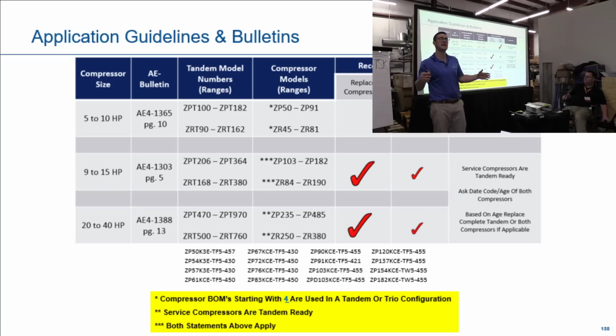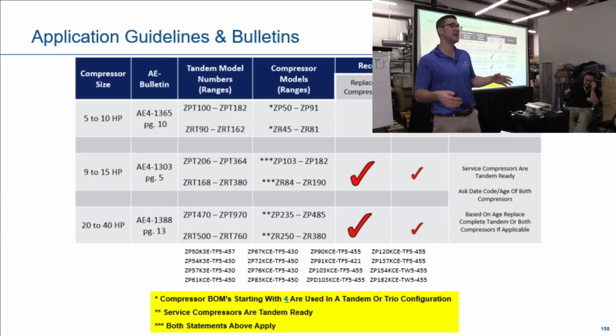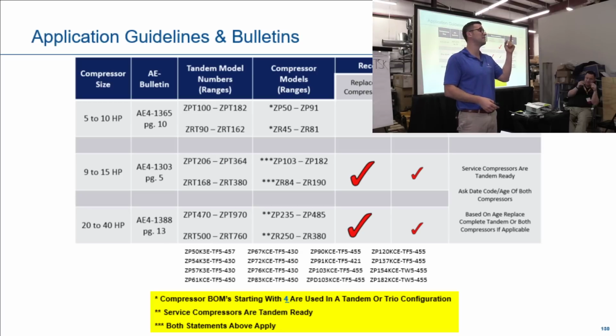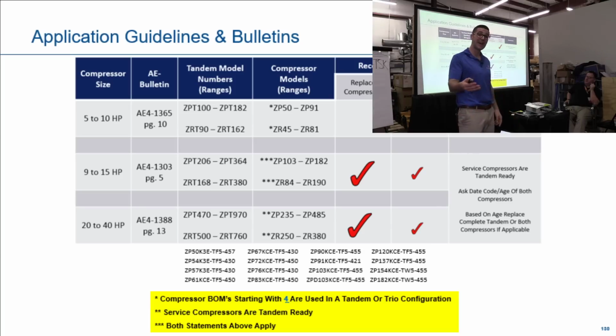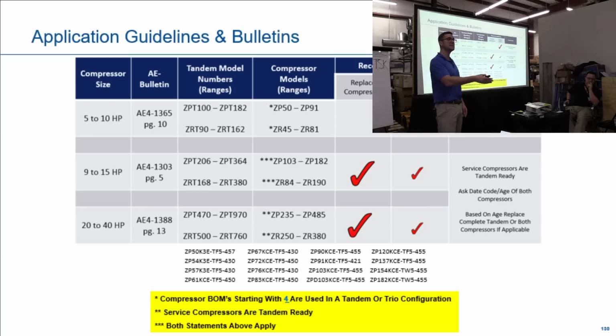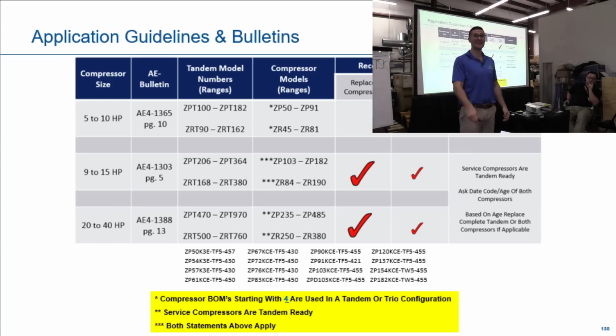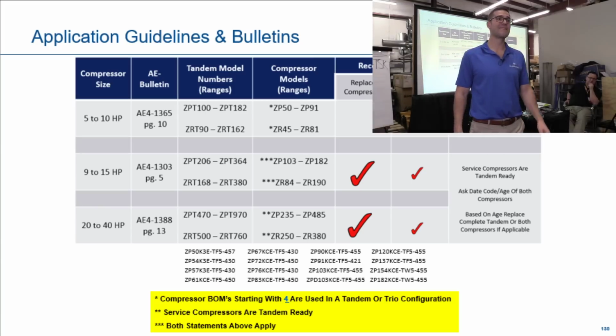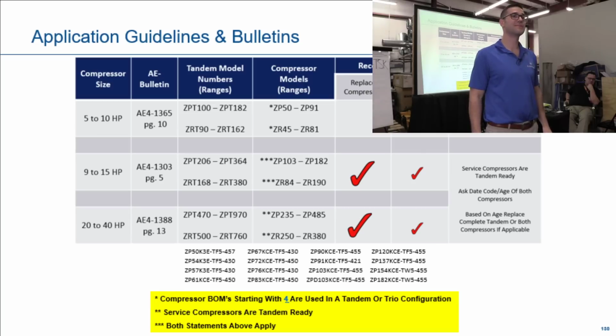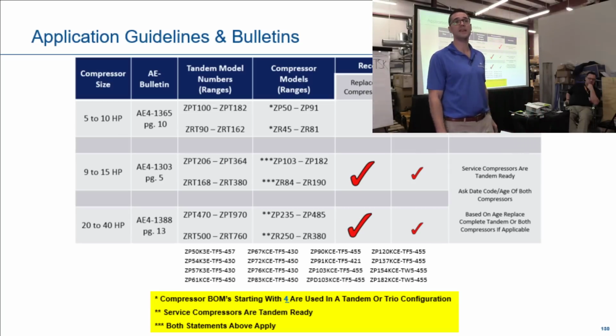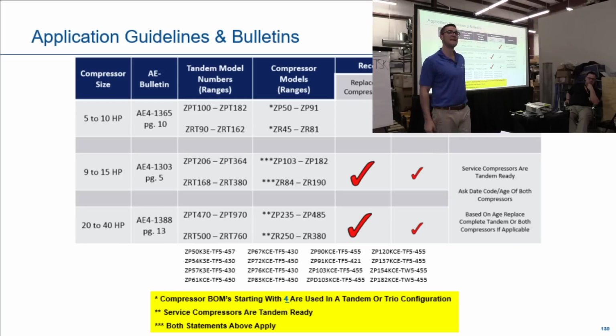So if you have a 10-year-old, 15-year-old system in a tandem set and one compressor fails on a burnout, should you replace the tandem? Yes, exactly, you should. But if it's only 6 months old and one fails because of flood back, should you replace the tandem? Probably not. Are you learning something here today? We have always been told to replace both of them, always. Not the case.